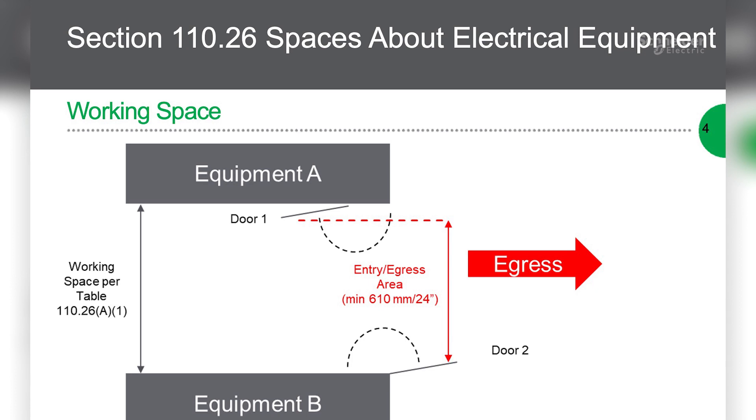In both cases, whether it's an e-house or other constrained locations, it's important to ensure that egress path. The measurement for the egress path is taken with doors open at the minimum 90-degree angle the code requires. Even if equipment can open more than 90 degrees, physical constraints of the electrical equipment room may prevent that, so you're back at square one and have to take that into account.